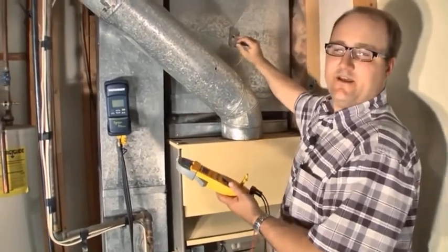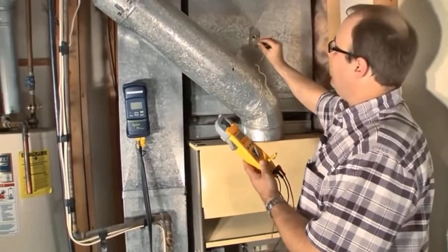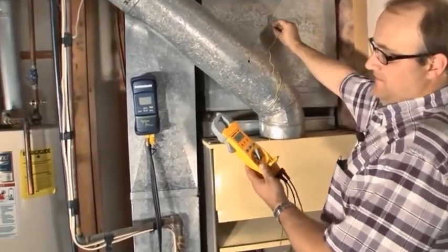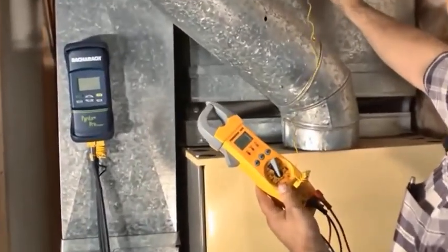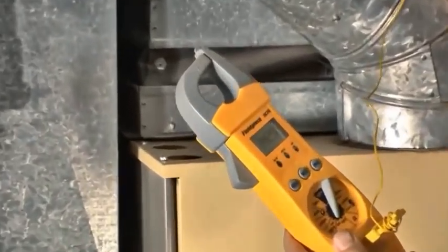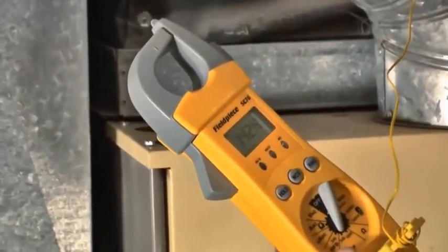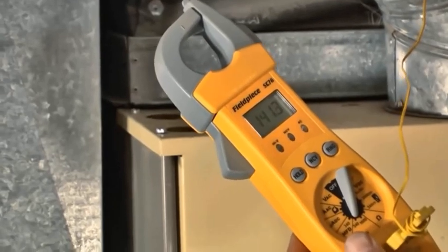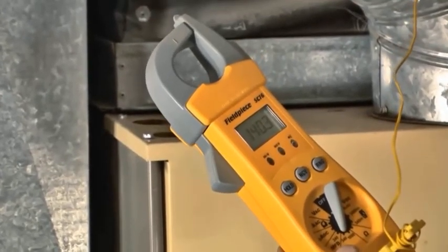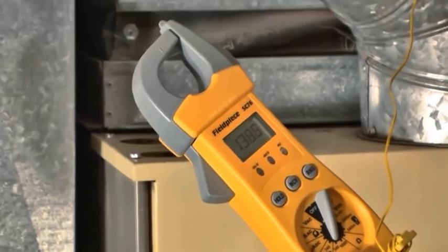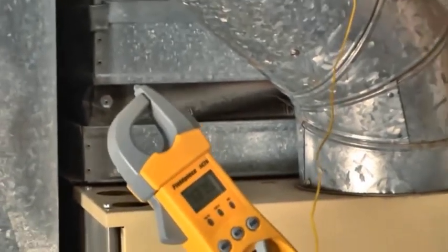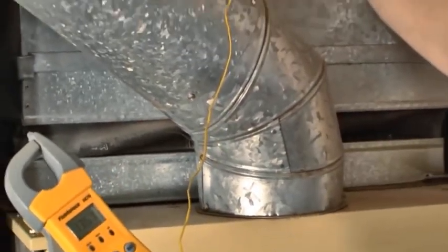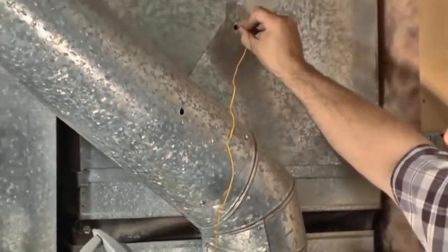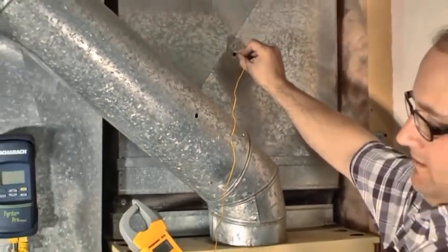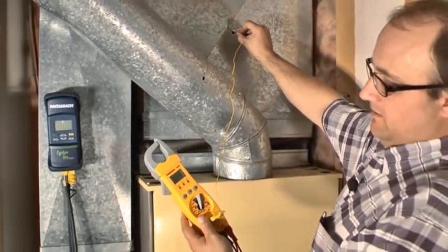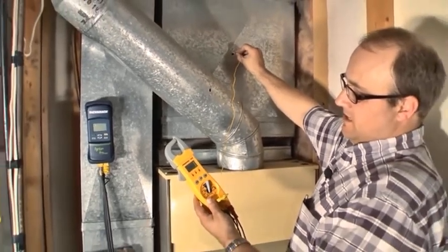Okay, right now I've turned the gas off, and all I'm trying to find out is what my fan off temperature is. So the fan's running, my gas is off, and there'll be a certain temperature. We want to see that fan come off at 85 to 95 degrees, and at the same time this is going to cool this furnace down so that I can pull the blower motor. When I pull that blower motor, I'm going to be looking up into the heat exchanger.